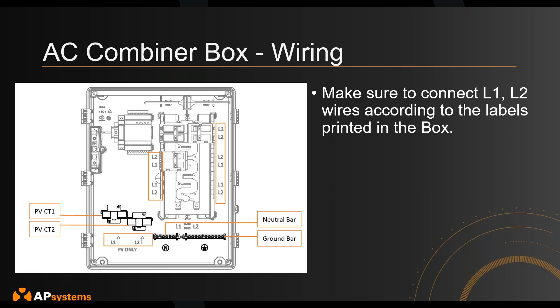Say, for example, CT1 is black wires, CT2 is red wires. You feed all the black wires into slots like L1. Notice there's a bit of alternating here because of the nature of the breaker box. Then you'd feed all the red wires into CT2, and red wires only go into L2. Just be cautious about that. We often see that the colors are correct, but where they're plugged in is often mixed up.